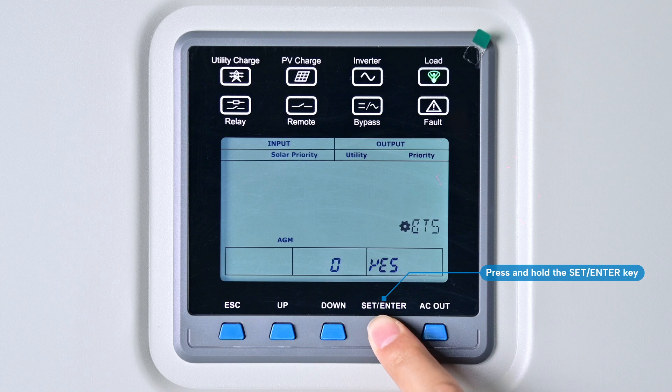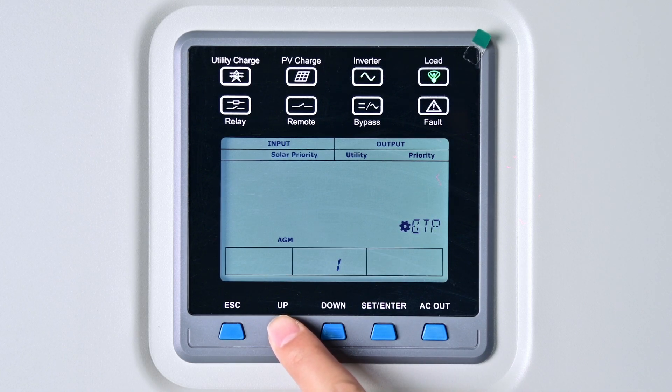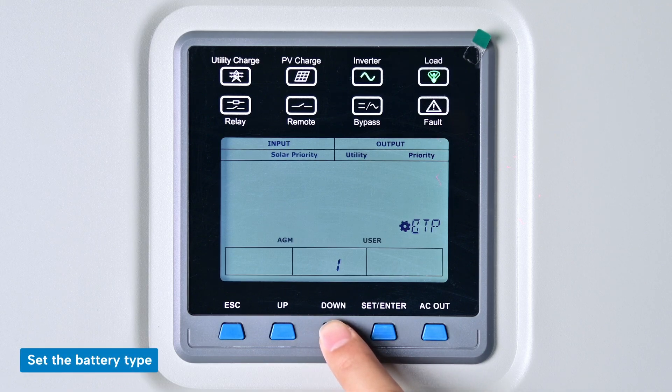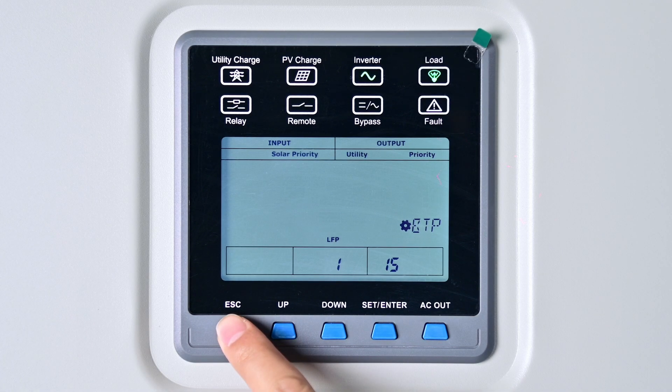To set the battery type, press and hold the Set/Enter key to access the general user parameter settings interface. Press the Up key to navigate to setting item 1 and enter the setting. Press the Down key repeatedly until LFP 15 appears, confirm it, then press Escape to exit.